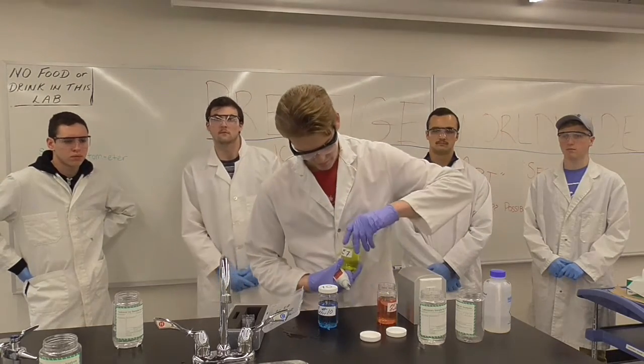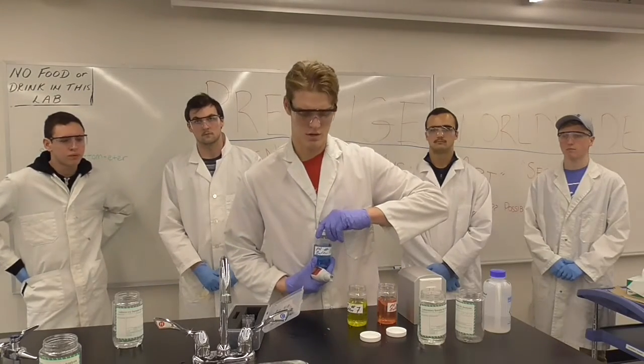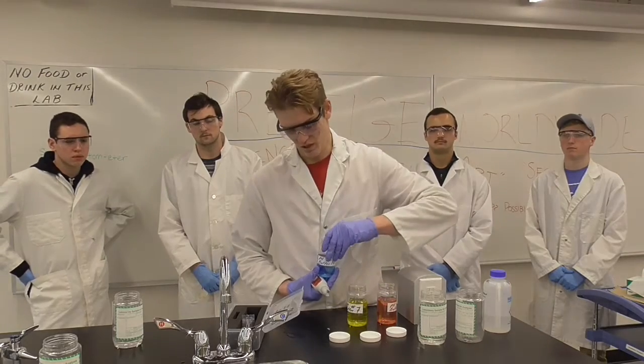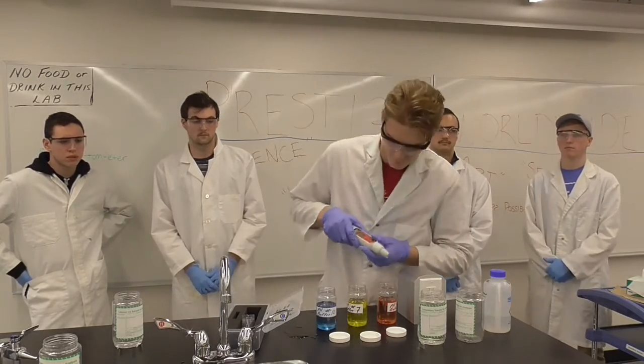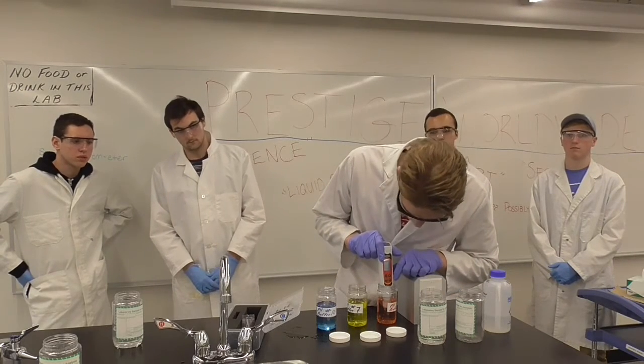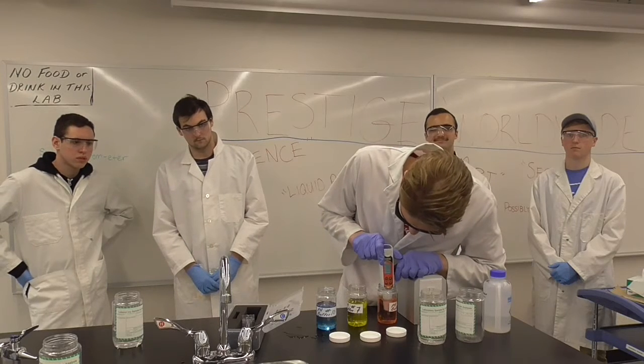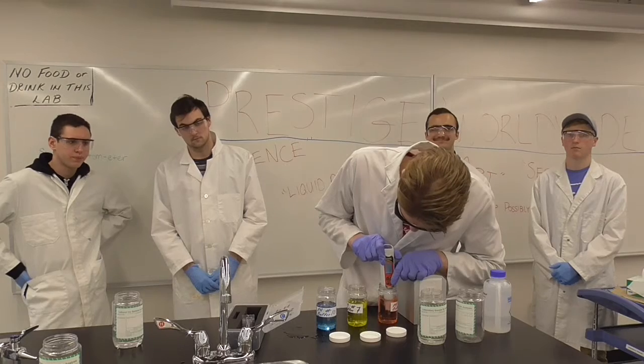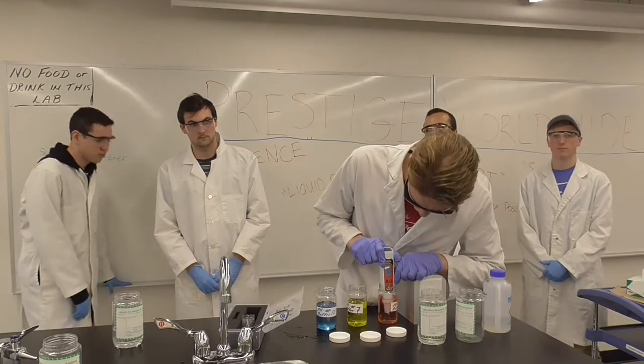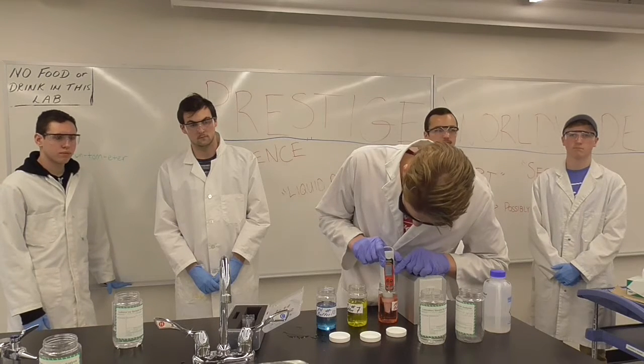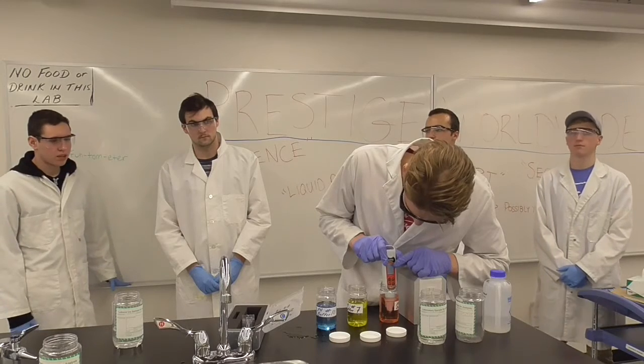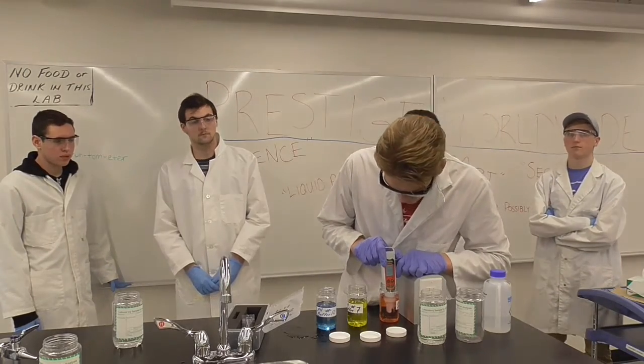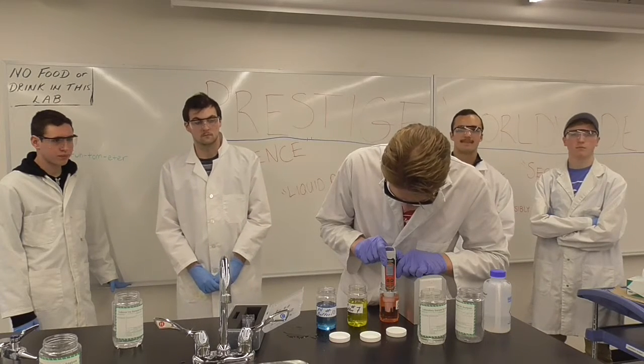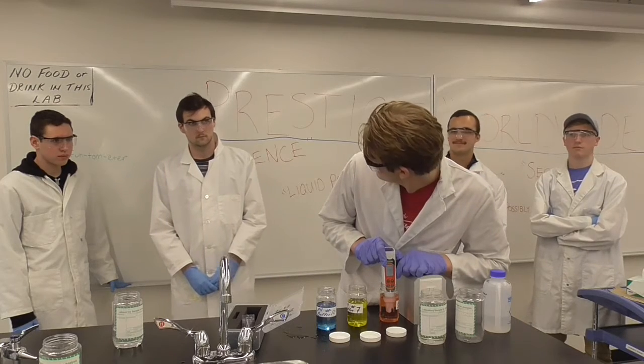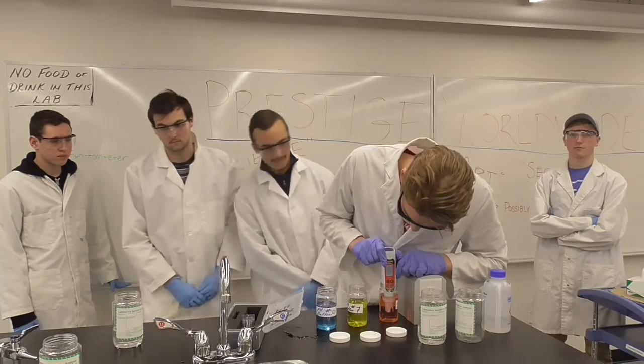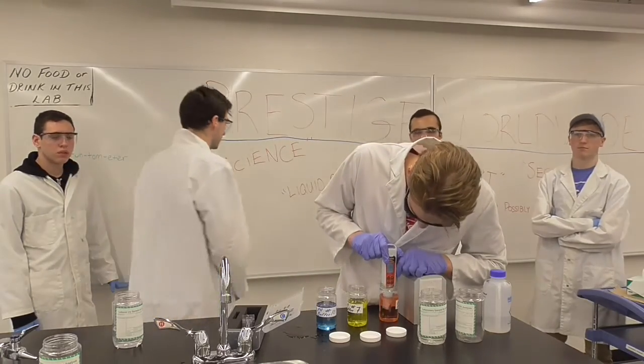And to calibrate the pH meter, you need to put it into calibration mode, which then will start to seek out the closest pH to it, and then it'll calibrate to that nearest pH. So if it's in the 4, it'll calibrate to the 4. So you just need to put it into the buffer solution just like that, and then you click calibration and hold. Then it will scroll through the bottom there, through the 3, 4, 7, and 10, and you need to wait till that clock right there is done and it turns into a check mark, and that's how you know that it's calibrated to that buffer. So there, the little check mark popped up.